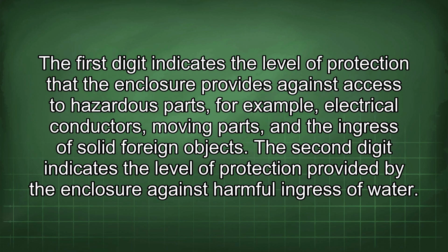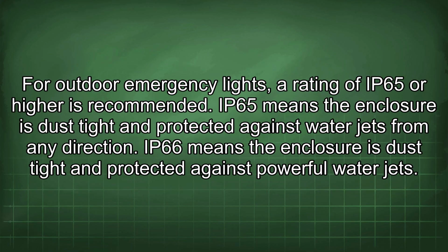The first digit indicates the level of protection that the enclosure provides against access to hazardous parts, for example, electrical conductors, moving parts, and the ingress of solid foreign objects. The second digit indicates the level of protection provided by the enclosure against harmful ingress of water. For outdoor emergency lights, a rating of IP65 or higher is recommended.